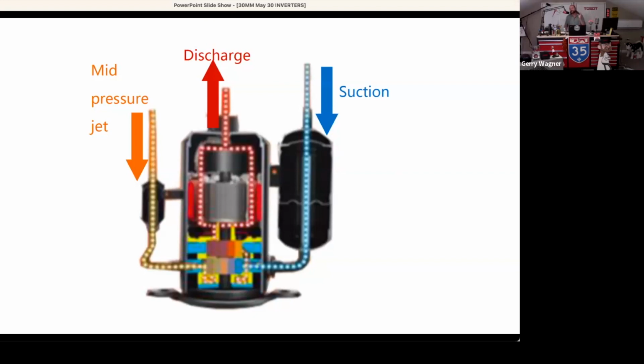There is a valve on the second injection port, which we call a vapor injection valve, which based upon outdoor air temperature and some other criteria will open. And that's what gives us what many companies call their ultra heat technology. So yeah, that's how we're scrubbing heat out of incredibly low outdoor air temperatures, with two suction ports at two different pressures, scrubbing energy out of those two different pressures. That's the key -- really interesting stuff, bringing heat pumps to another level with low outdoor ambient heating.